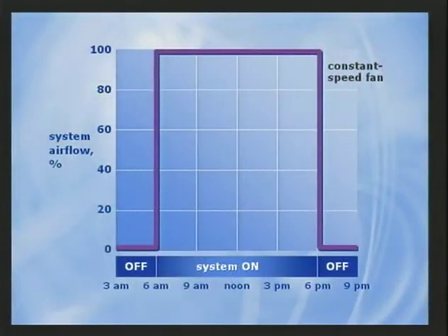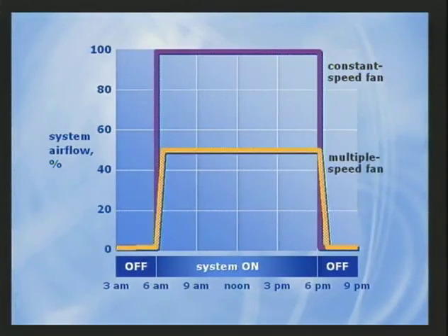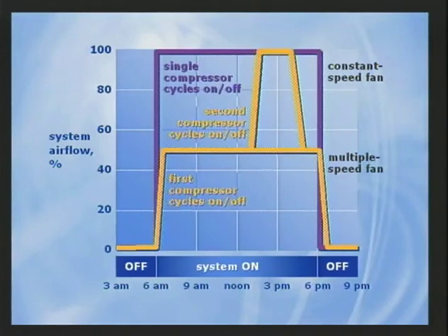Now, similar to a chilled water terminal unit, stepping down the fan speed as the first step to reducing cooling capacity can improve the dehumidification performance of a single zone DX unit. A traditional unit with a constant speed fan operates the fan whenever the classroom is occupied. A unit with a multiple speed fan attempts to operate at low speed whenever possible. This reduced supply airflow results in a colder supply air temperature at part load and improved dehumidification performance. When the cooling load increases to the point where space temperature rises above set point, the unit controller automatically responds by switching to high-speed fan operation.